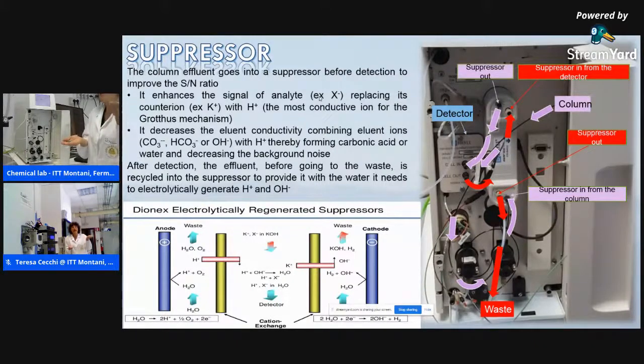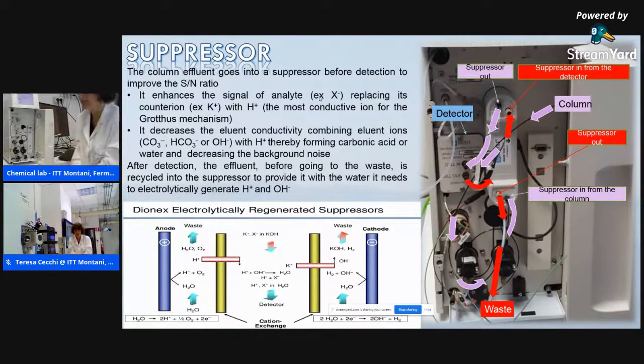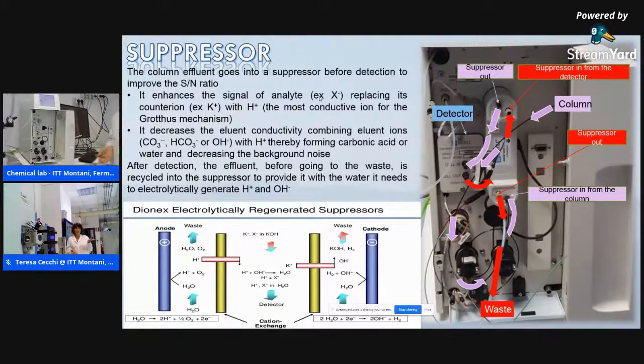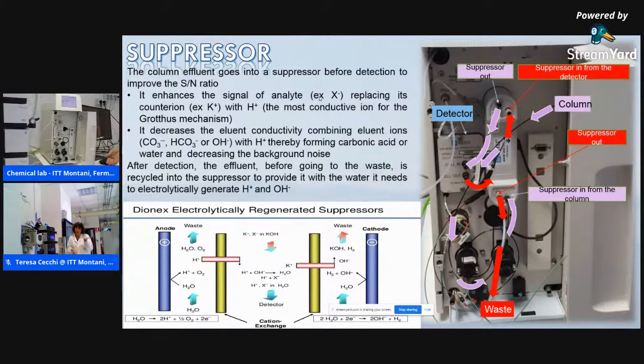If I combine H plus from the electrolysis of water with OH minus, I get water. So the background conductivity due to the hydroxyl ions is drastically decreased. In the meanwhile, the H plus, the analyte ion negatively charged, for example, fluoride, will exchange its counter ion from sodium or potassium to H plus. This means that fluoride conductivity with H plus is increased while the background eluent conductivity is sharply decreased. This way, the signal to noise ratio is really increased and the limit of detection can be decreased. So we can see also trace concentrations.